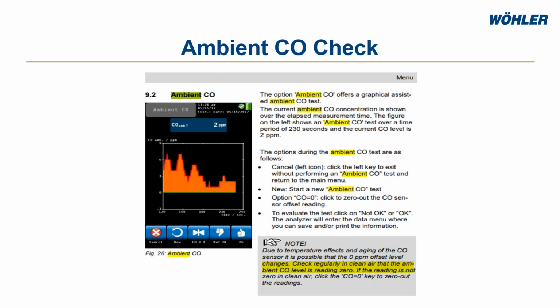Then there's the ambient CO check, which is on all of the analyzers. Let's say you get a call from a customer who says they're feeling lightheaded and haven't had their furnace or boiler checked in a while - that's a perfect time to use the ambient CO check. The analyzer essentially turns into a carbon monoxide checker, graphing the CO it's seeing and giving you a readout. If you're just detecting ambient CO, use this feature instead of the combustion screen - it's more accurate, and it even lets you zero out the CO sensor. You can put this in your test report and deem it okay or not okay, giving your customer more insight when you hand them the receipt printout.